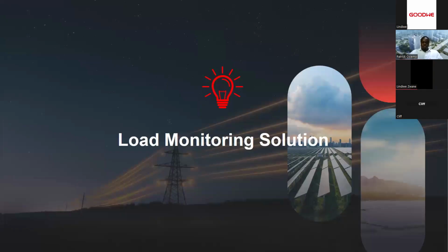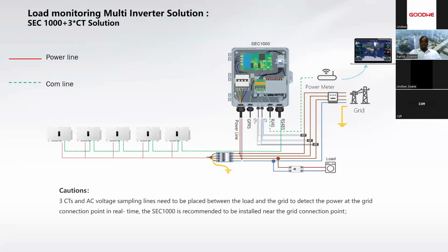Now, if you look into the load monitoring solutions, we deploy the same control box. With the SEC 1000, you install it the same way as for the export limit, and in the same portal you'll be able to monitor the load consumption from the grid. That is the EasyLogger Pro, which is in the SEC 1000, getting a reference from the GM 3000 smart meter, also in the SEC 1000 control box. And with reference to the PV generation, you'll be able to know how much you're consuming from the grid.